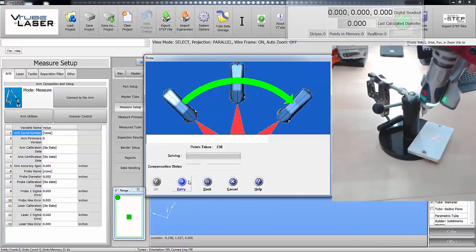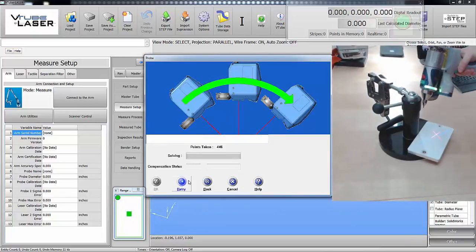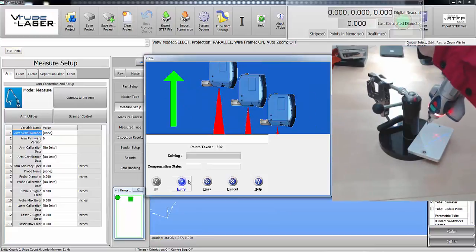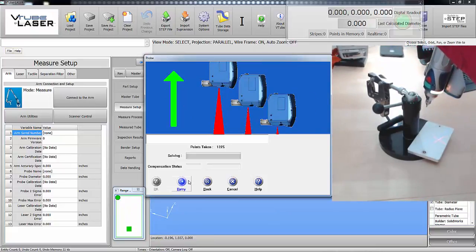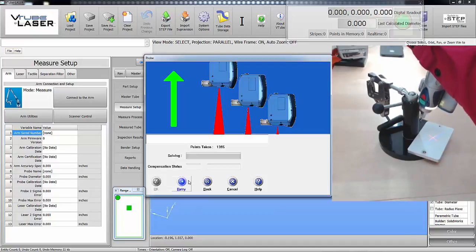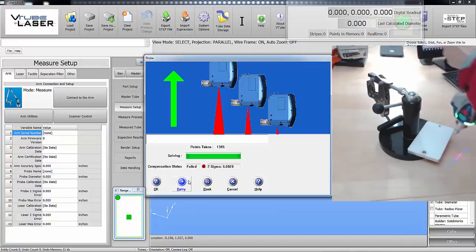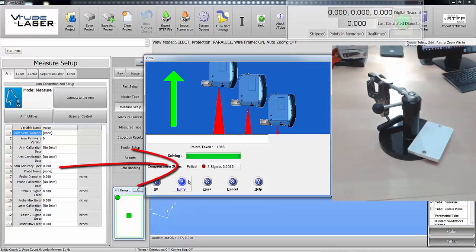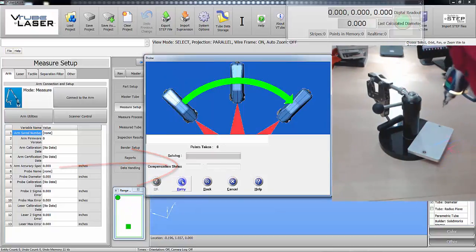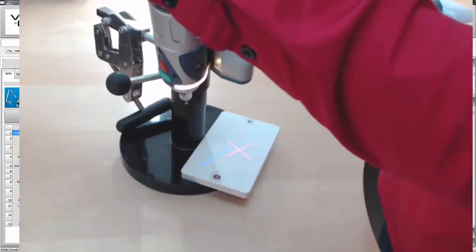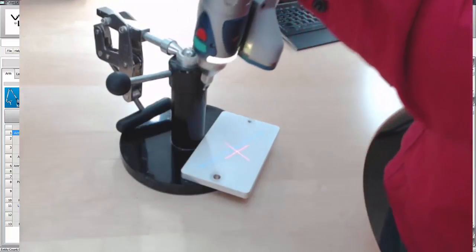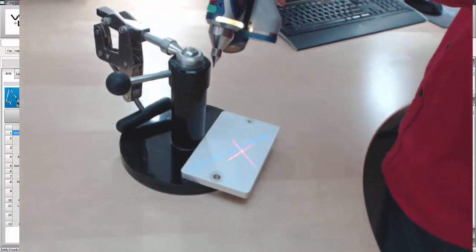First you'll want to move in line with the grid. Then you'll want to move over the line, and then you'll want to go straight up and down like this. Press the red button to allow the FARO driver to calculate the compensation. In my first attempt here, the compensation failed. Well, the FARO driver is very strict about what numbers it accepts. So that's okay, just hit retry and do it again.